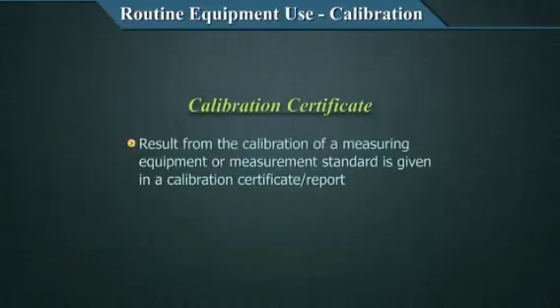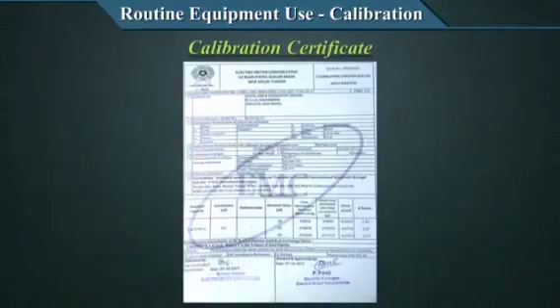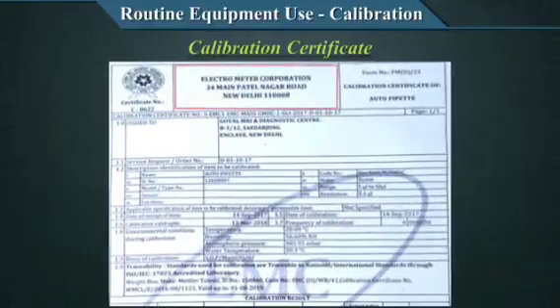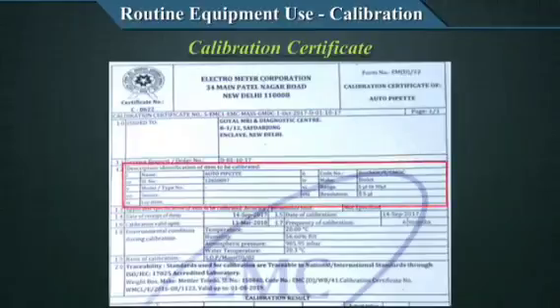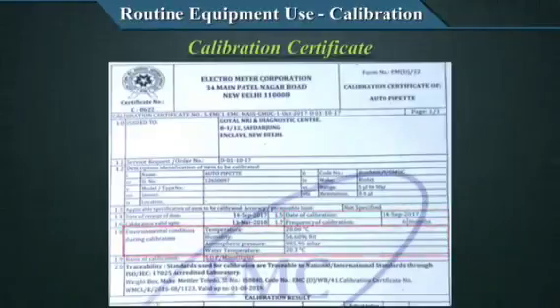This is a reiteration. The result from calibration of a measuring equipment or measurement standard is given in a calibration certificate or a calibration report. It can be either in a hard copy or an electronic format and should include a minimum of these things: name and address of the calibrating agency, unique identification of the certificate, name and address of the client, the identification of the equipment calibrated by the manufacturer or the brand and type, and the unique identification number, date the calibration was performed, the environmental conditions during calibration, standards used with their validities, calibration uncertainty, traceability.